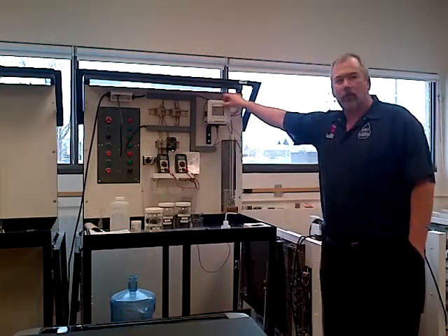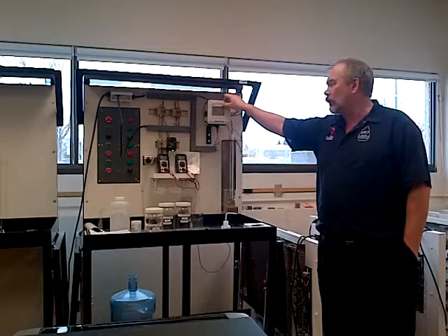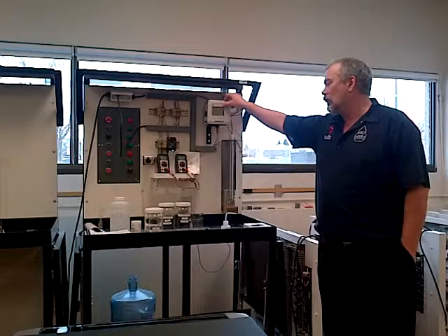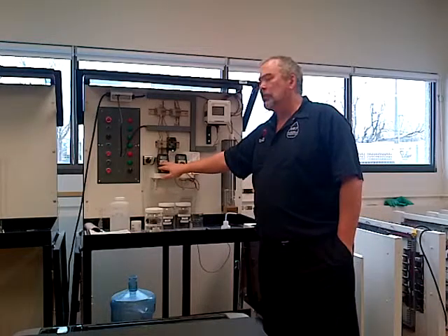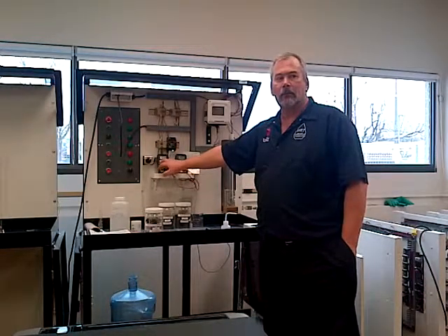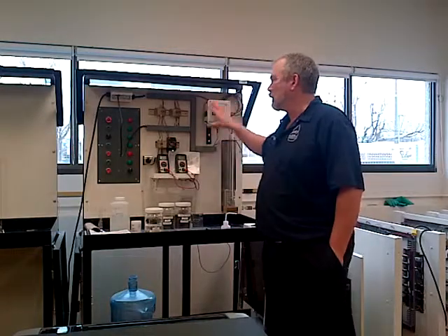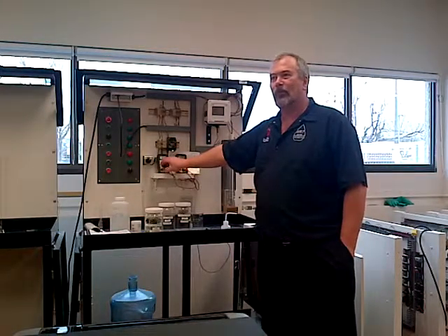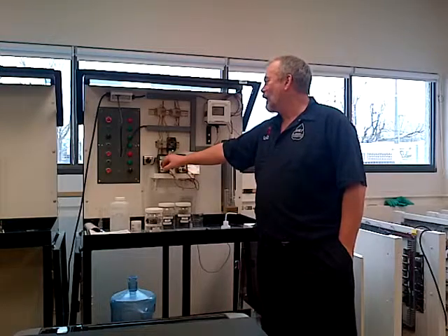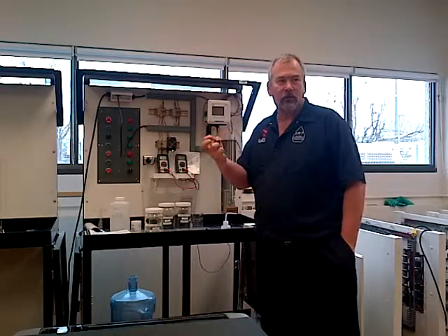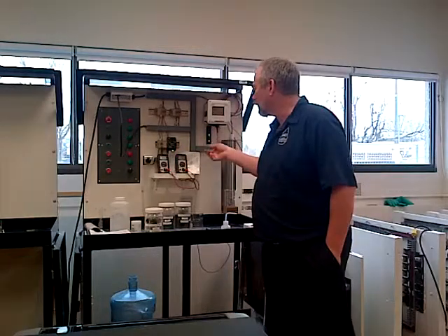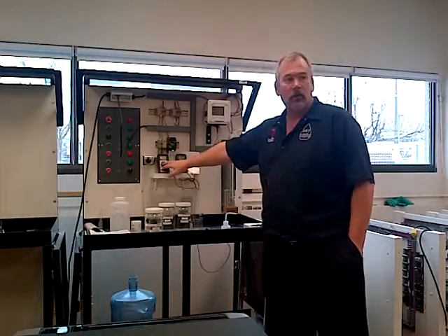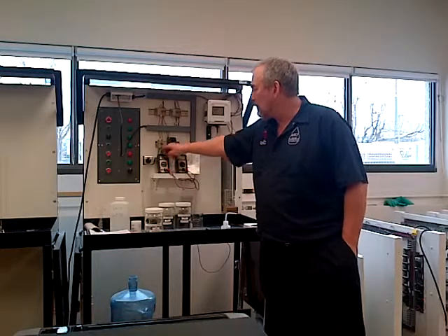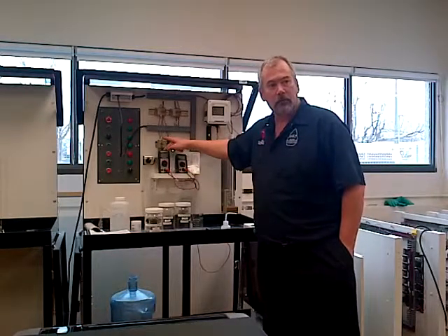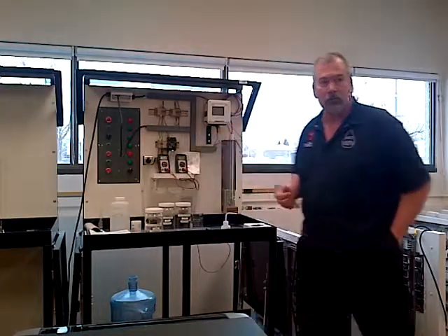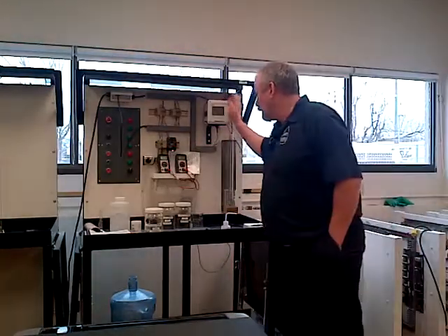There's a fault on this one. Don't worry about it too much. What that fault is, it wants to see a high impedance measuring device coming from its output. High impedance means a super high resistance coming off. So the 4 to 20 milliamp signal coming from here to your SCADA system or PLC is being simulated by this cheap little meter, and it doesn't like that. It wants a proper PLC. So don't worry about that.